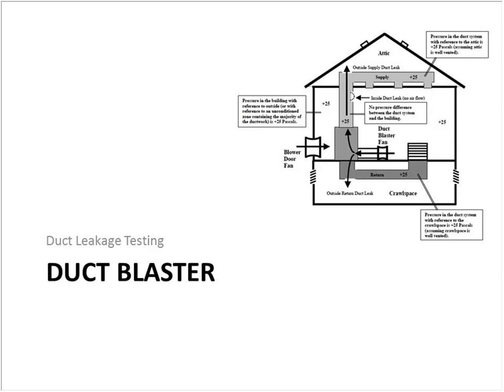You also have the option of testing prior to construction completion at the rough-in stage. So you've got all your ducts in place, the air handler is in place, but maybe you don't have all the drywall up, or the transition boots don't have grills in them, obviously. And at that time, you might think, well, we'll test at that time so that we can determine where our leaks are and we can address those. We've experimented with that quite a bit, and it's extremely difficult for two reasons. One is it's hard to find leaks even though you can see the ducts, especially if the house isn't fully enclosed and there's any wind outside. Using tracer smoke, it's almost invisible at that point. But also the fact that the total duct leakage then drops to 3 CFM in that condition, and that's a standard of total leakage.